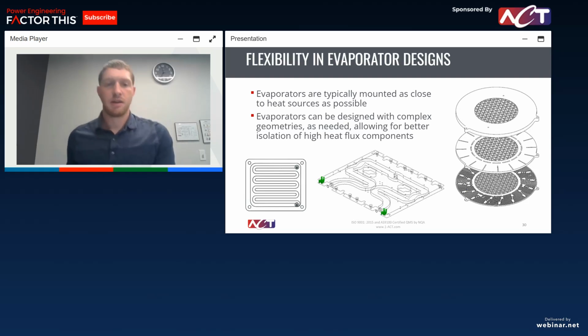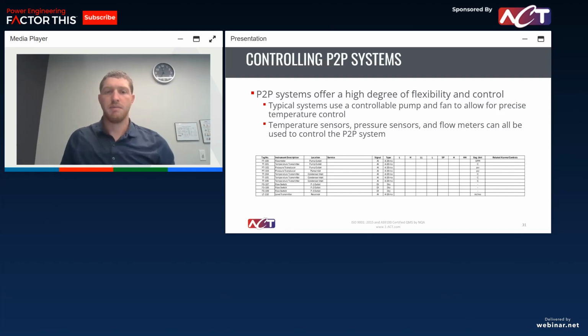And then kind of getting into control. Typically when we're controlling a pump two-phase system, we have a pump that can be modulated in how fast it's running, and the fans for the condensers if we're using a liquid to air heat exchanger. We'll use temperature sensors, pressure sensors, and flow meters that are giving input back to a PLC, and what we control will depend on the application. Oftentimes what customers want is to really control our evaporator temperatures, the junction temperatures of the electrical components.